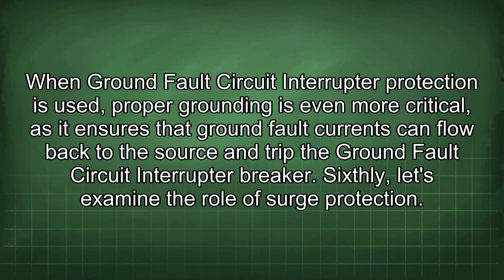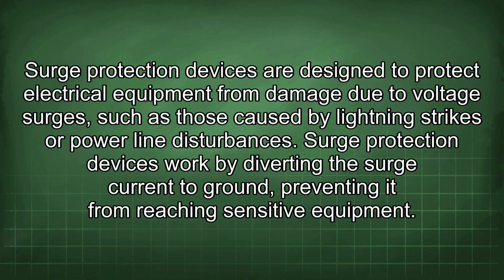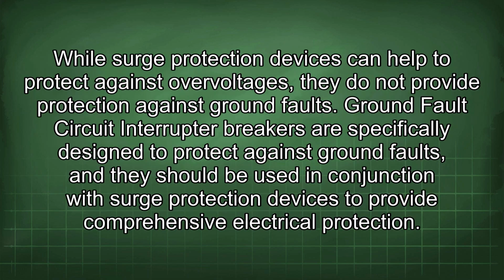Sixthly, let's examine the role of surge protection. Surge protection devices are designed to protect electrical equipment from damage due to voltage surges, such as those caused by lightning strikes or power line disturbances. Surge protection devices work by diverting the surge current to ground, preventing it from reaching sensitive equipment. While surge protection devices can help to protect against overvoltages, they do not provide protection against ground faults. Ground fault circuit interrupter breakers are specifically designed to protect against ground faults, and they should be used in conjunction with surge protection devices to provide comprehensive electrical protection.